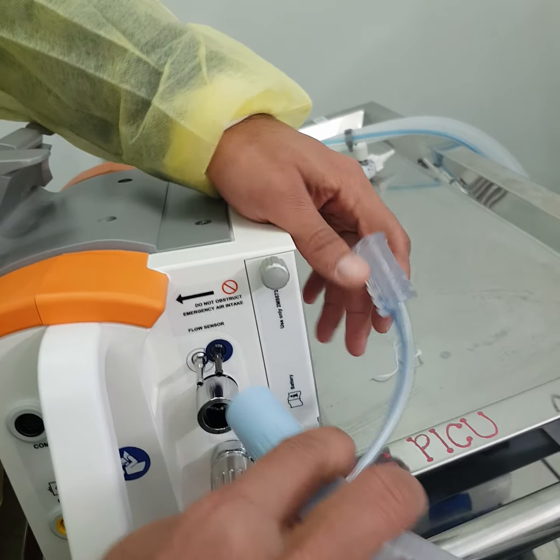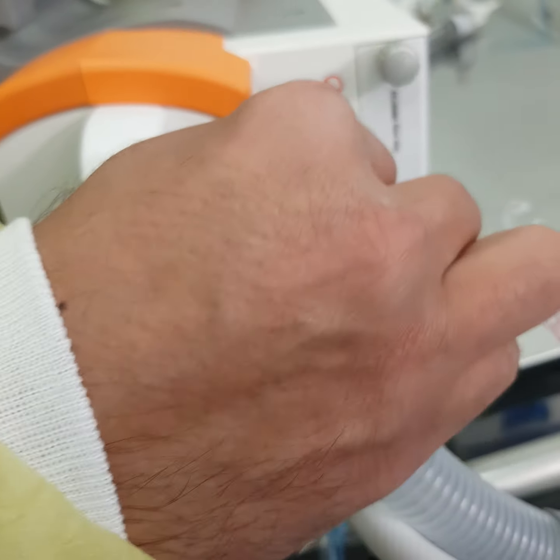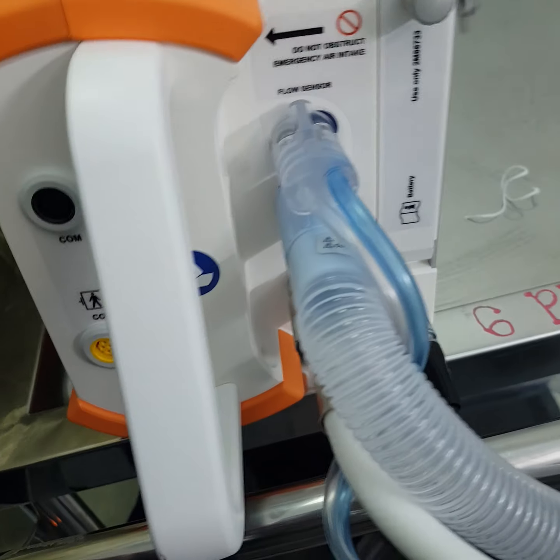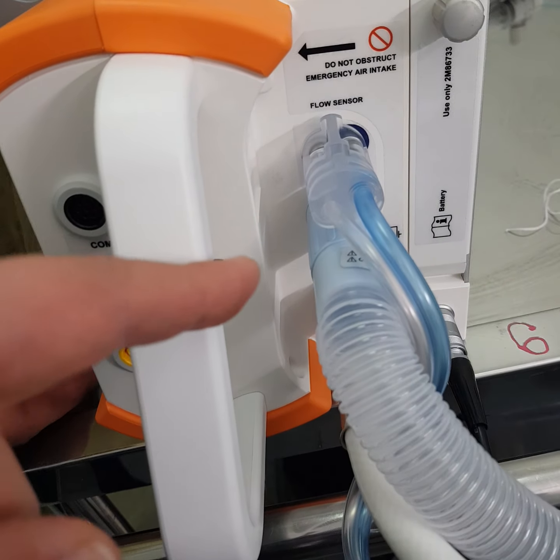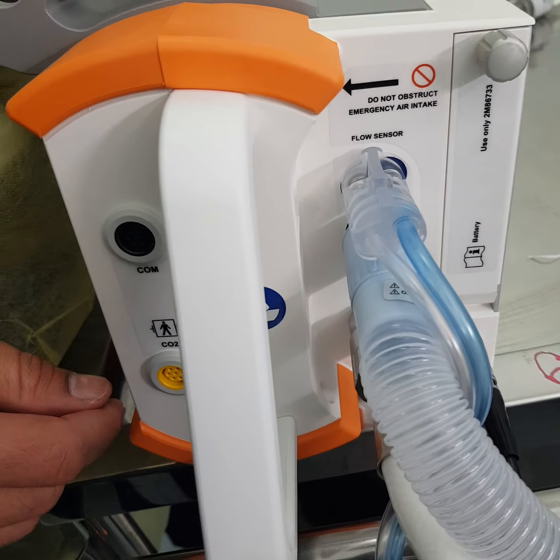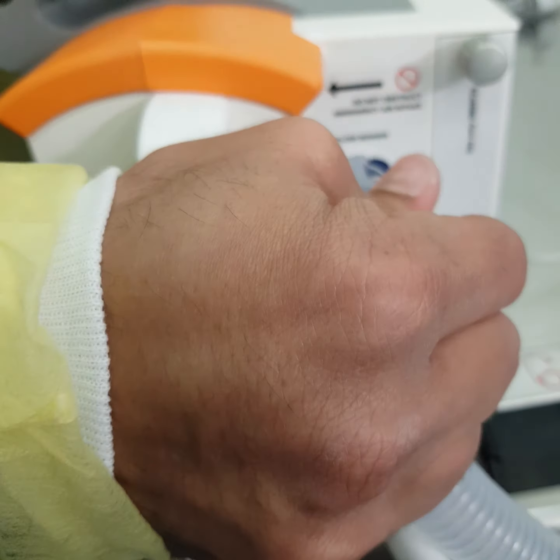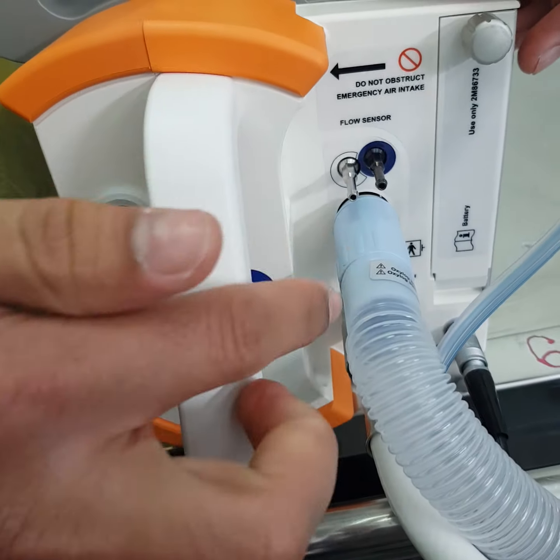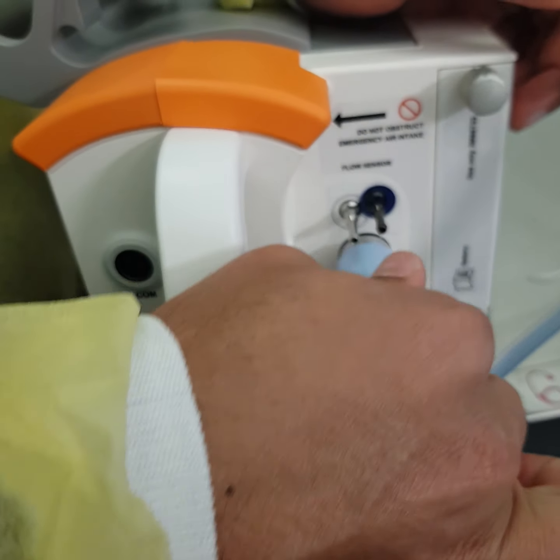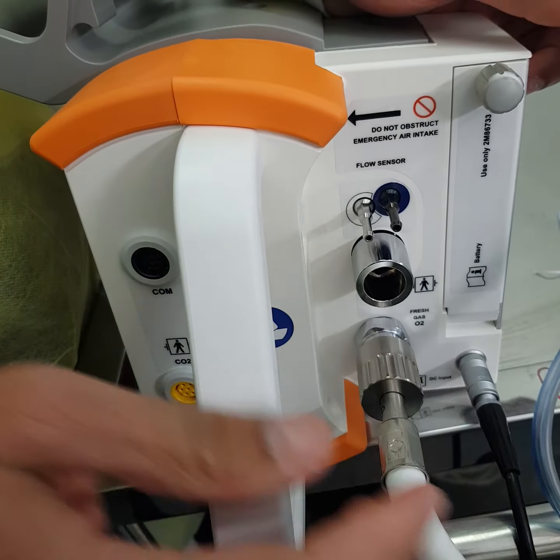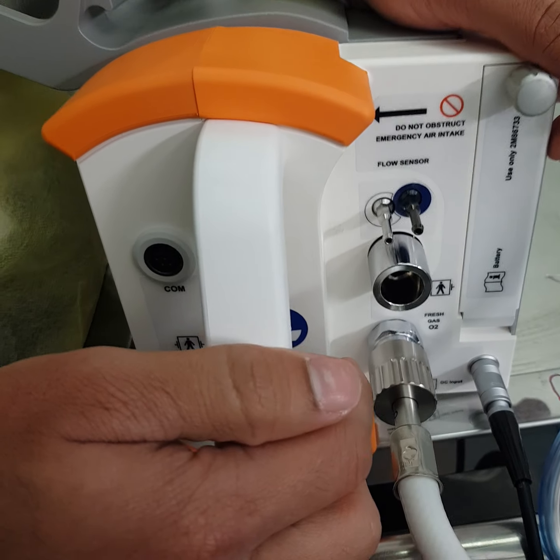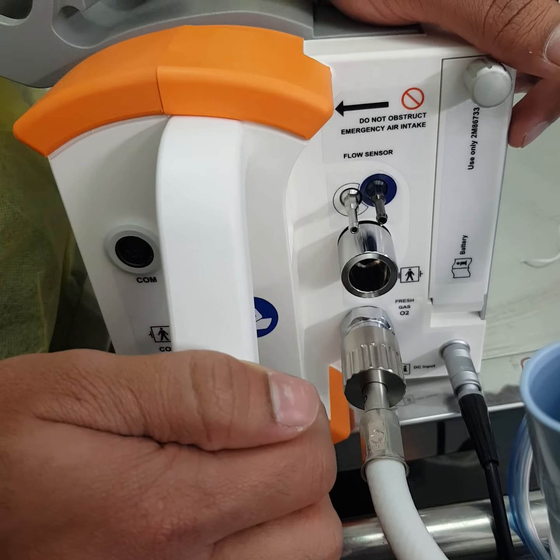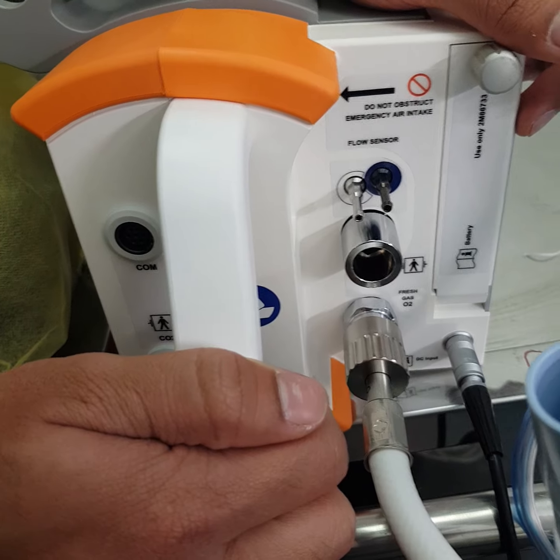So right now we are using an adult disposable circuit, which has to be fixed: the bigger tube to the bigger port, and the smaller tubes to the smaller flow sensor ports. Once you are ready, this inlet and this outlet are for pediatric and adult, so this is multi-purpose. You can use pediatric or adult circuits, and also reusable and disposable circuits can be used with the same port.